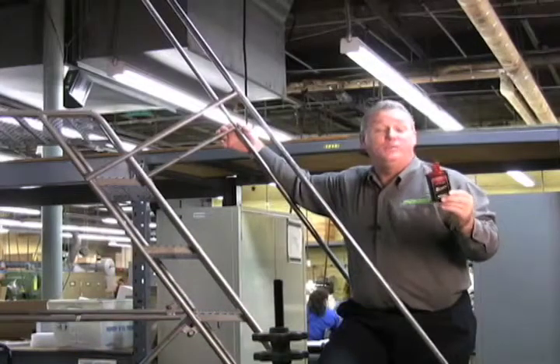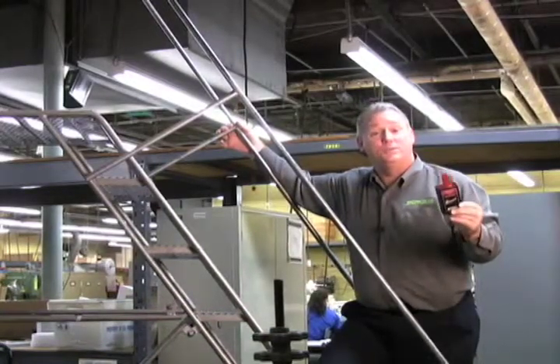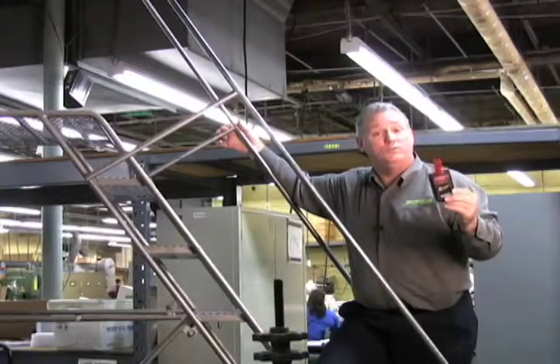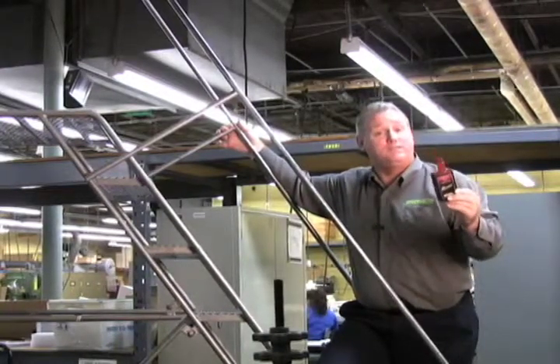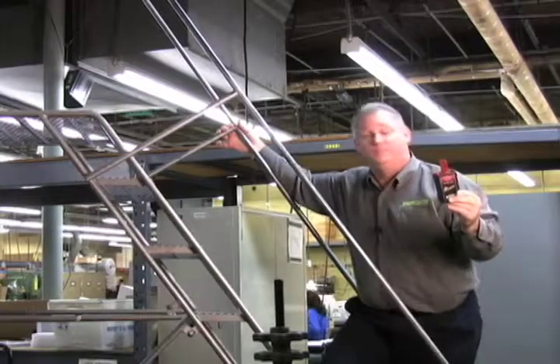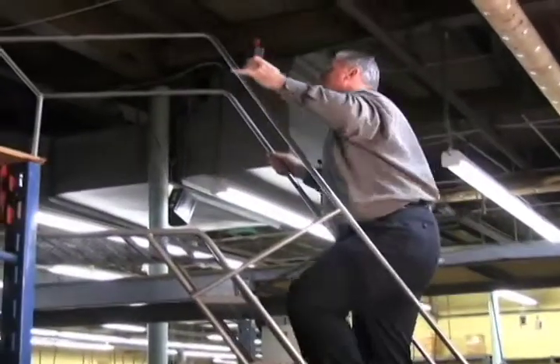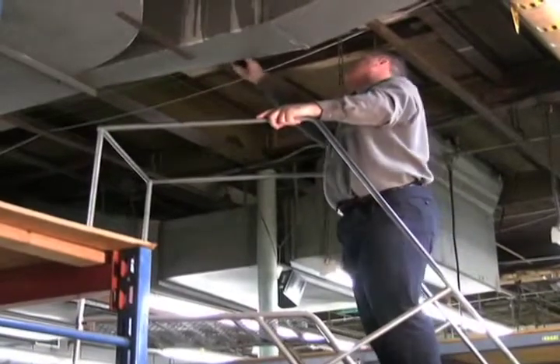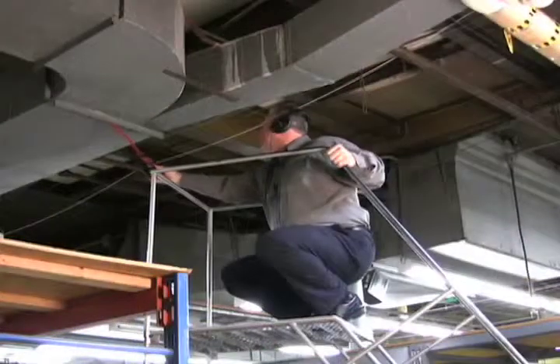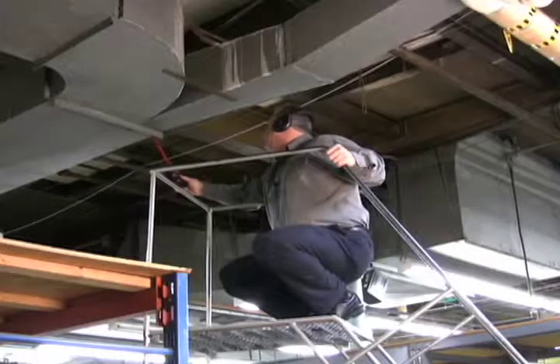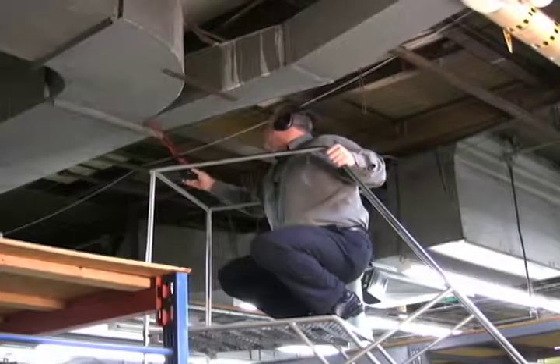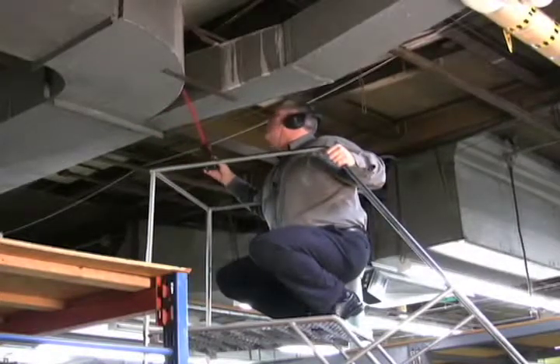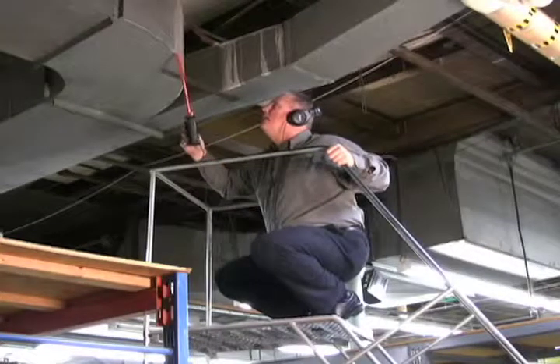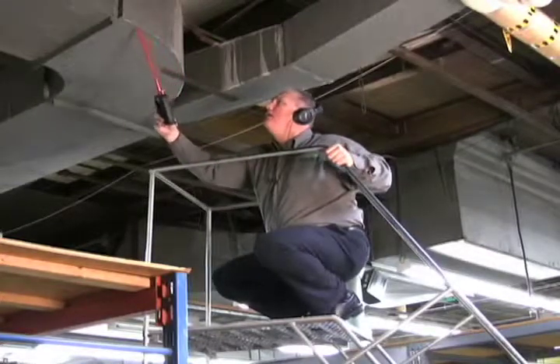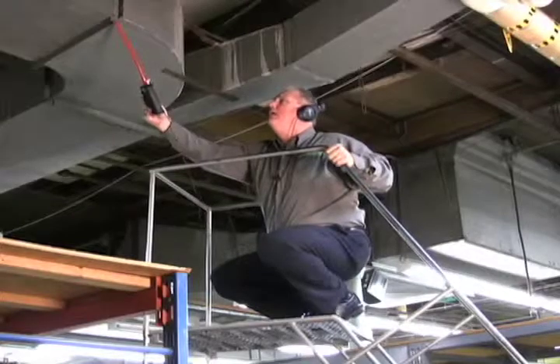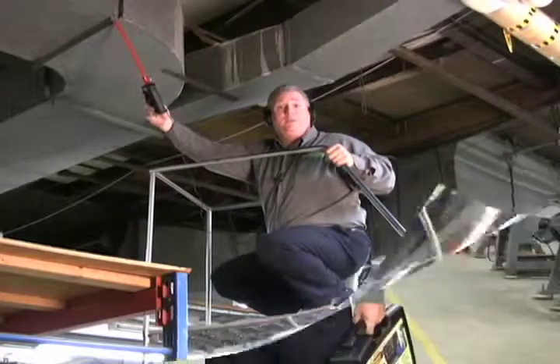Earlier we explained to you how the emitter can work for non-pressurized enclosures. Here in our facility we're going to insert this into our AC ductwork to check for cracks in the line or leaks at the joints. Here we have a leak in our joint.